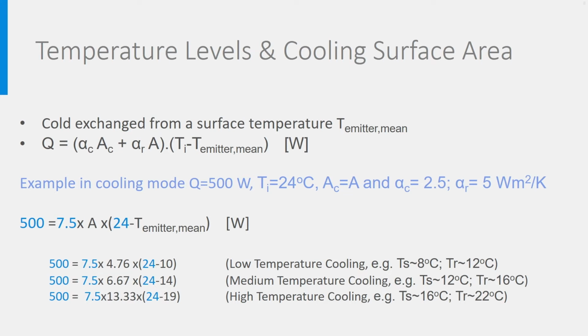In the second example, the cooling panel has an average temperature of 14 degrees, with, for instance, a supply temperature of 12 and a return temperature of 16 degrees. This leads to a surface area of 6.7 square meter. And in the last example, the panel temperature is only 19 degrees, leading to a surface of more than 13 square meter. So, the higher the temperature of the cooling panel, the higher the needed surface area. The temperature levels given here correspond to what we call low temperature cooling, medium temperature, and high temperature cooling.